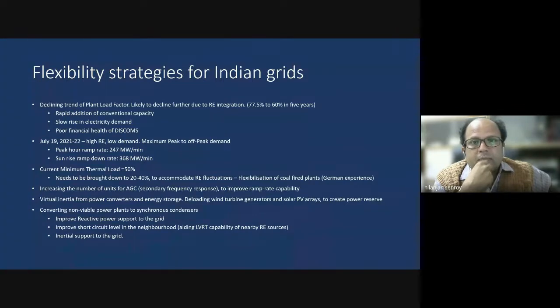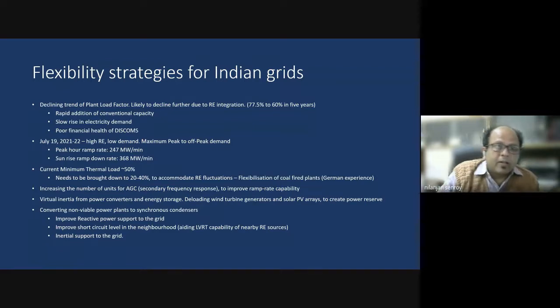So generally, thermal power stations have ramp down, ramp up limits of about 2 to 4% of the rating. So a 500 megawatt unit cannot ramp up or ramp down at more than 10 megawatts per minute. So this 368 megawatt per minute is a very difficult number to achieve. So the only solution is that, because you have a large number of thermal generators and hydro generators, you must enable AGC, secondary frequency response, in order to improve the ramp rate capability.